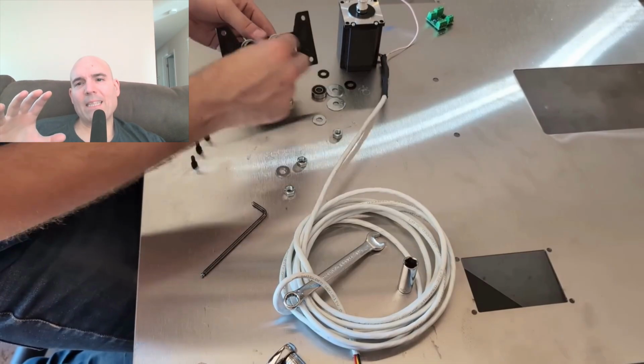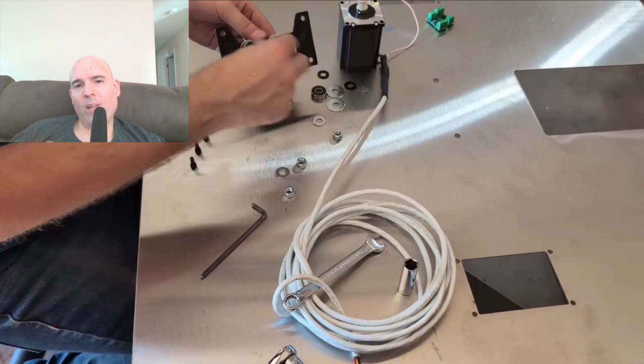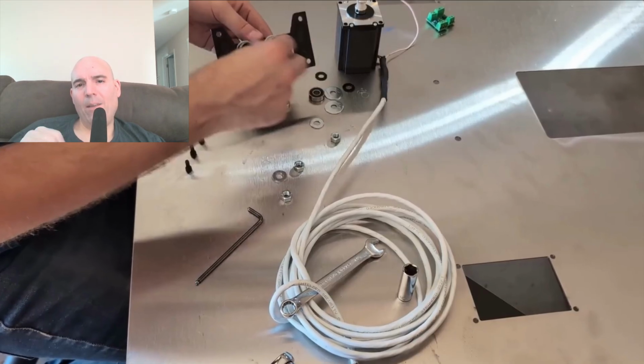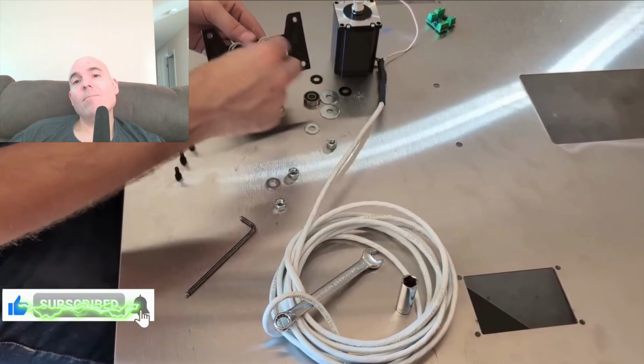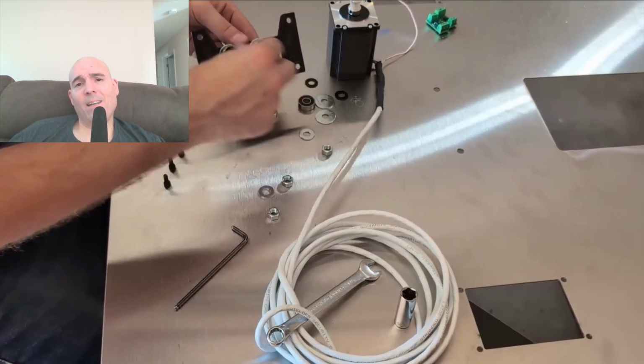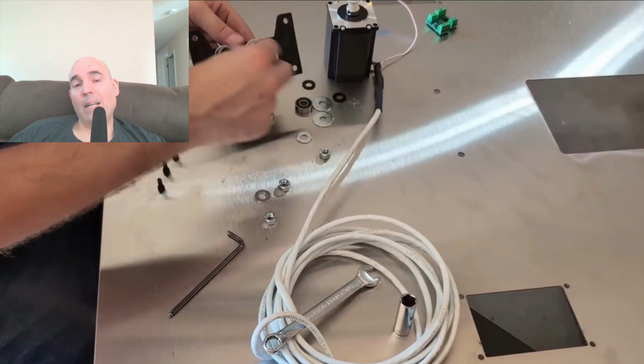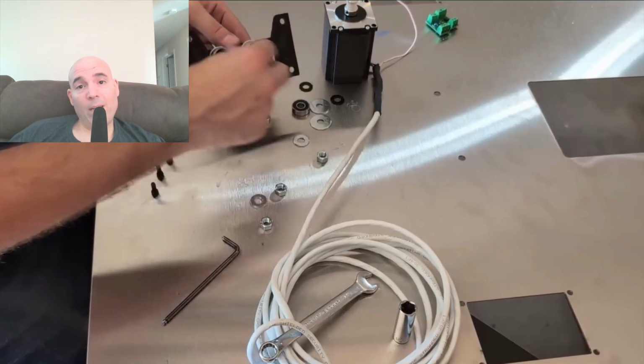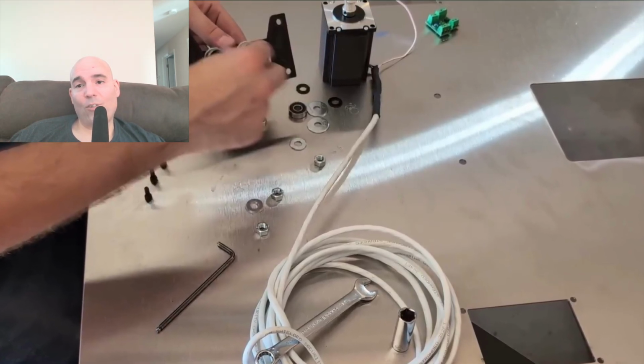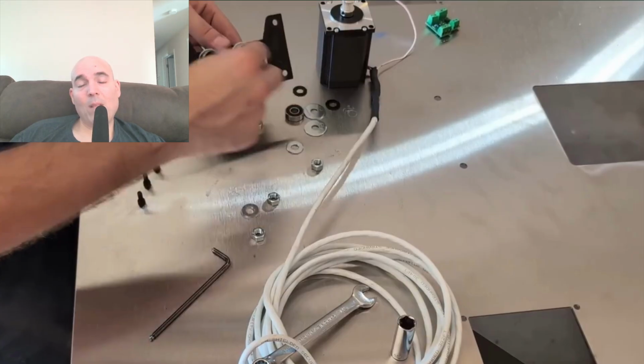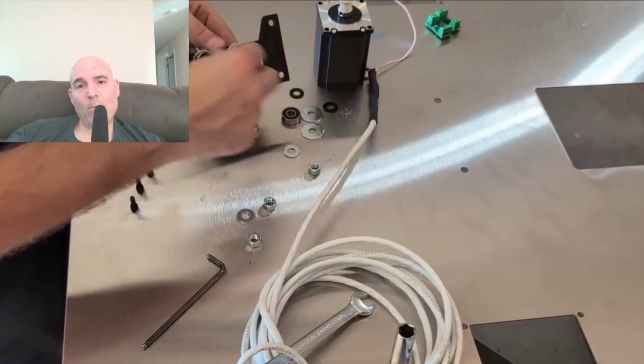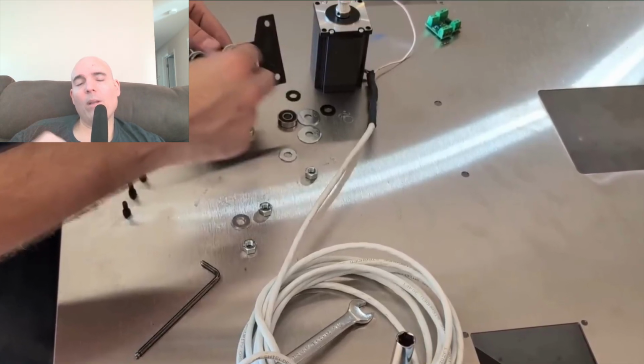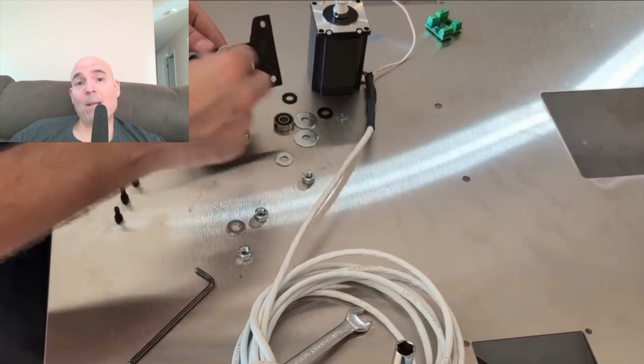All right, guys, so we can see the lead coming off of the shielded cable where he's attached them to his motors. He feels he's doing this correct. I'm asking you, is he? Think about it. We've just identified that his chassis has a coating on it. He never mentioned at all about removing that coating. He never discusses anything about grounding the chassis. Yet we have a shield drain that's terminated on the end of where the motor is. This is not best practice.